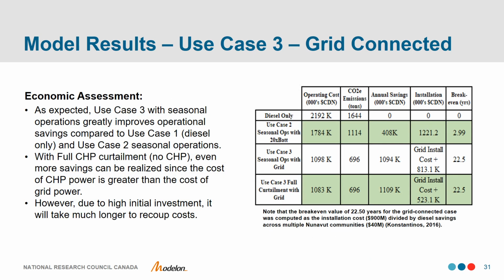Looking at the economics, as expected, use case 3 with seasonal operation greatly improves operational savings compared to use case 1 with diesel-only operation and use case 2 with seasonal operations. However, with full CHP curtailment, even more savings can be realized, as in this case, the cost of producing CHP power is greater than the cost of purchasing power from the grid. However, due to higher initial investment, it will take much longer to recoup costs.